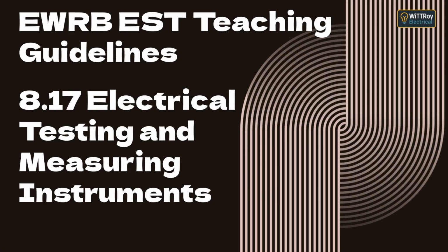Topic A. Purpose of electrical testing and measuring instruments. Electrical testing instruments allow us to measure voltage, current, resistance, continuity, and insulation resistance, and to verify correct polarity and earthing. Their main purposes are: 1. To confirm that circuits are correctly wired and safe to energize. 2. To detect open circuits, short circuits, or insulation faults, and 3. To monitor performance and ensure compliance with New Zealand standards. Without accurate testing, you can't prove your work is safe, and as we learned under Regulation 16 of the ESA, all work must be tested before being put into service.